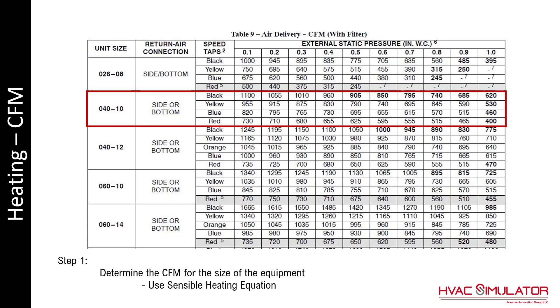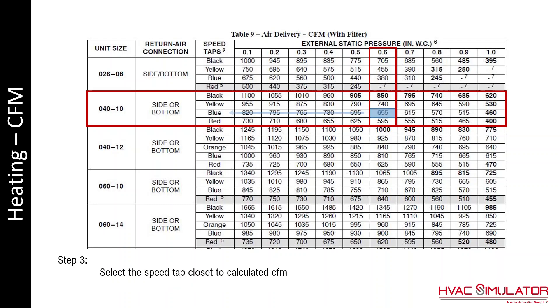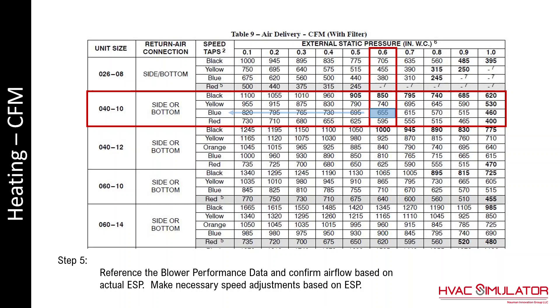In the next example, a 40,000 BTU furnace is used. The calculated value was 639 CFM, therefore 655 is the closest value. Measure the actual external static pressure and make the necessary adjustments. If the actual external static pressure was 0.5 inches of water column, then a technician would have to make a judgment call — whether to leave it on the blue speed tap or use the red speed tap. At 625 CFM, which is close to 639 CFM, either one would be a good choice.